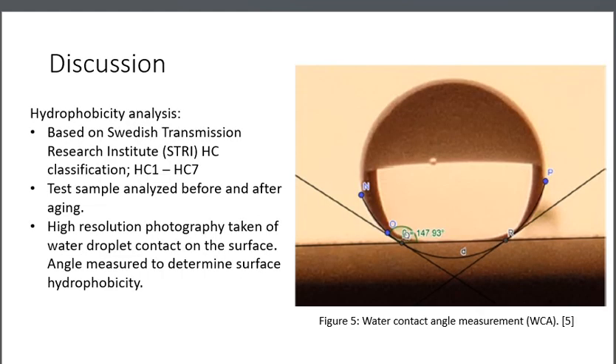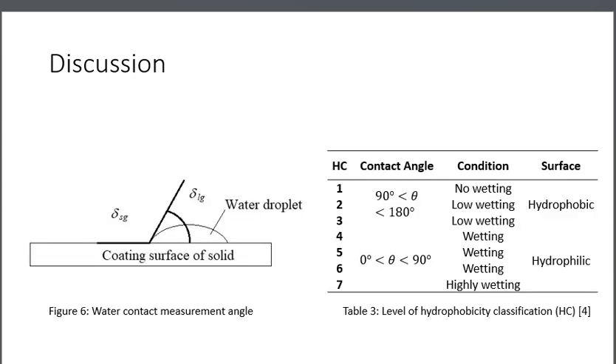Hydrophobicity was evaluated using water contact angle measurements. The surface condition was classified based on the STRI hydrophobicity classification, which ranges from HC1 to HC7. Lower HC values indicate strong hydrophobicity, while higher values indicate deterioration. High-resolution images of the water droplets on the coating surface were captured and the contact angles were measured to determine the hydrophobic behavior of the coating before and after aging.